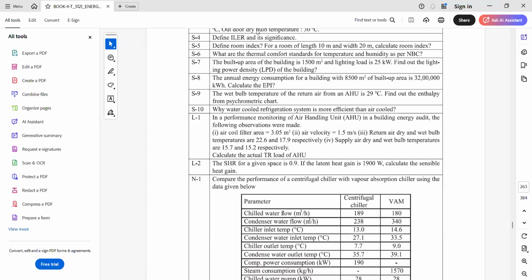Yes, okay. So basically these are the principles of why water cooled systems are more efficient than air cooled systems. In a water cooled system, the cold water is supplied very close to the service point itself. Whereas in air cooled, we are cooling and treating the air in a farther location and bringing it, so there is a loss or picking up of heat, due to which our temperature differences are very high. For example, if I use an air cooled chiller, I probably have to cool to 7 degrees, whereas with a water cooled chiller, even if I bring it at 12 degrees, at the end point it will be serviceable.